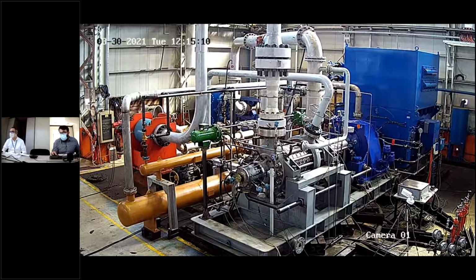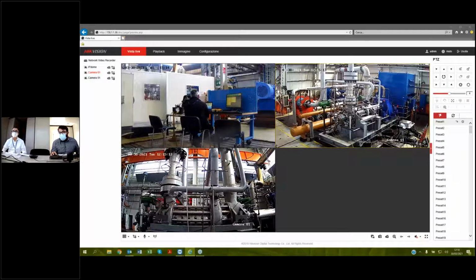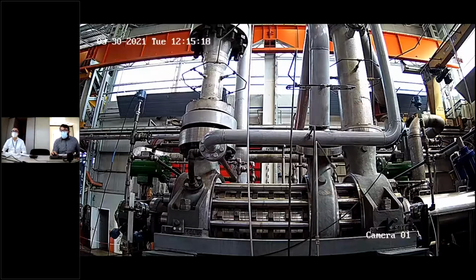Good morning, nice to meet you. Now let's check more closely the installation to check the instruments together. On the video you can see the three lines where the water flows. On the left we can see the discharge line with the four taps pressure for the discharge pressure. The second line in the middle is the bleed off line with another 4-tap installation for bleed off pressure. And the first on the right is the suction line with another 4-tap pressure.